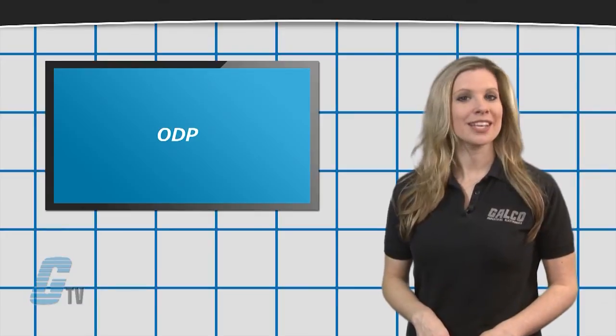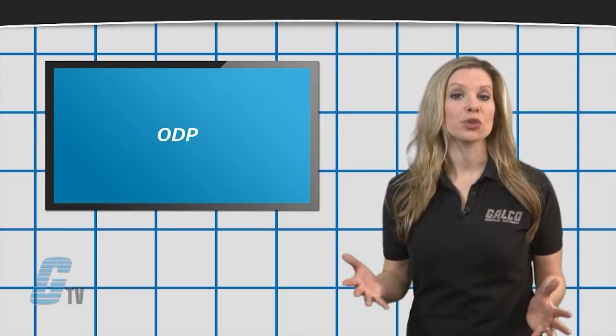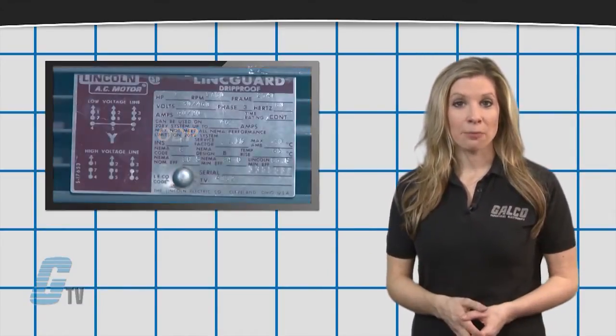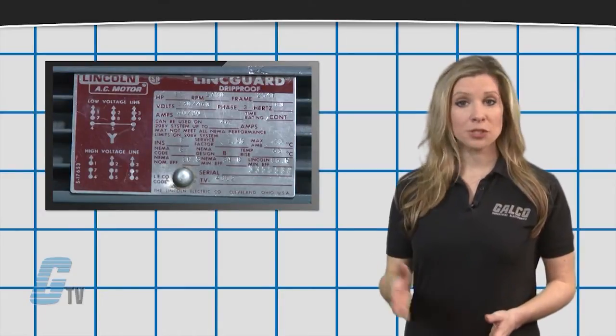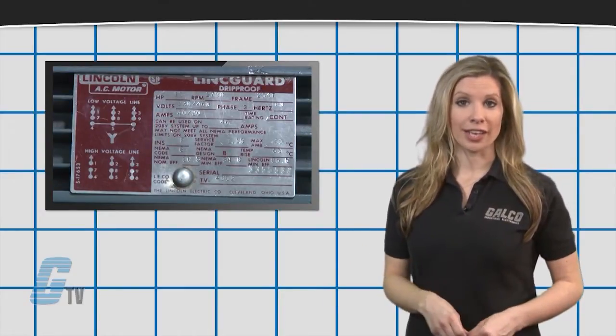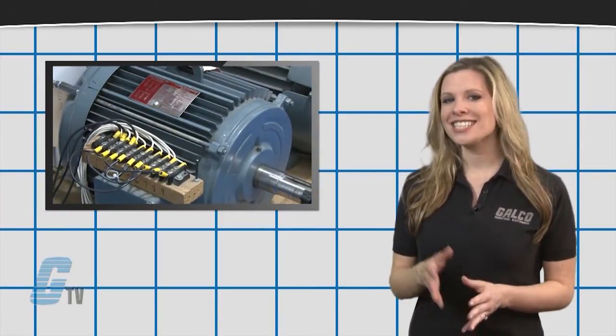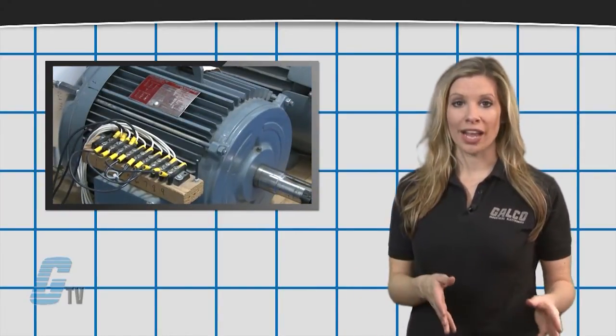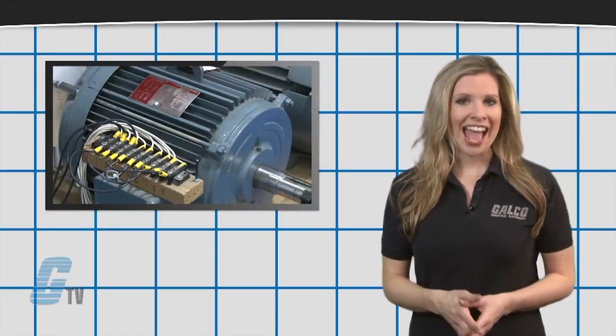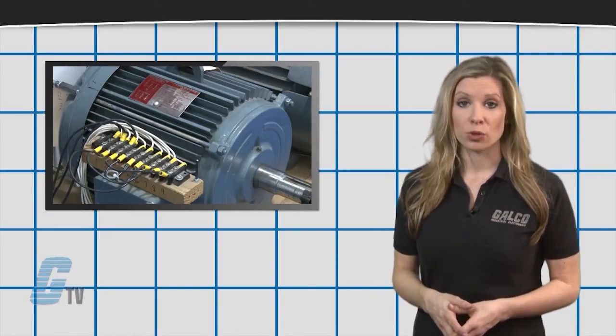The ODP enclosure is open and allows for air to cool the motor. They can protect from falling water up to an angle of 15 degrees. Although this offers a great deal of protection, it does not protect from wind-driven rain or air contaminants and is not recommended for outdoor use.